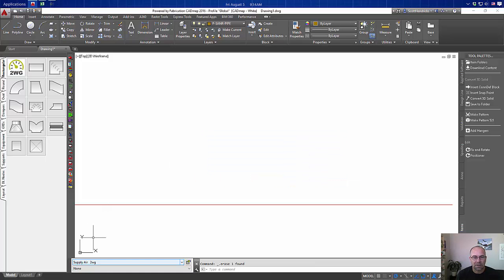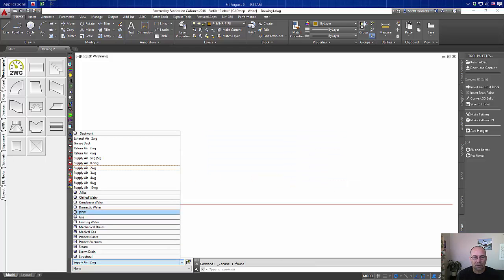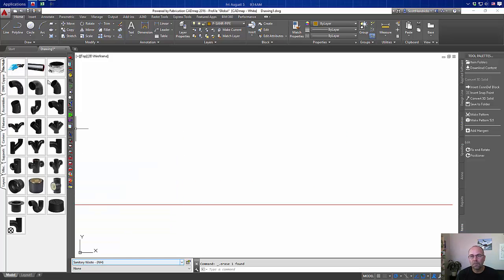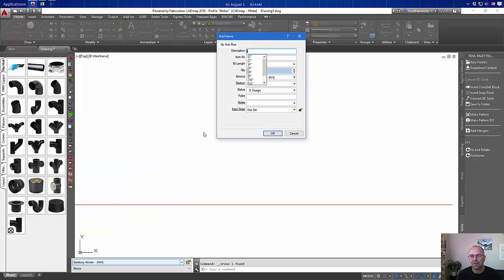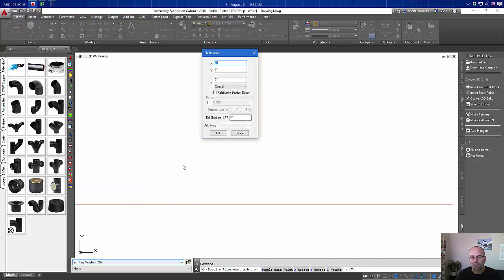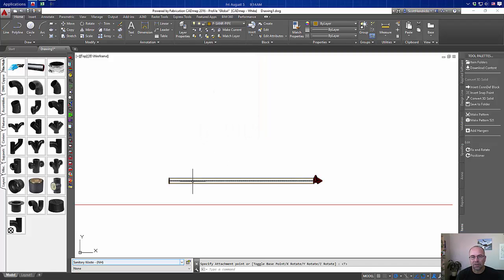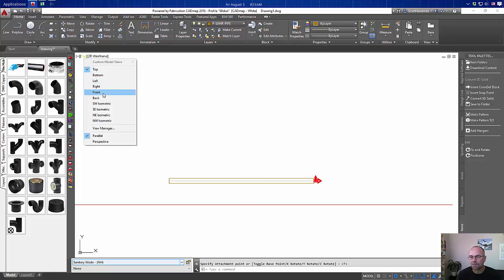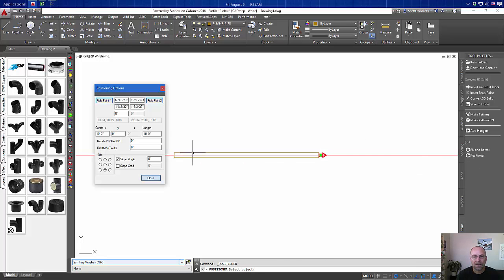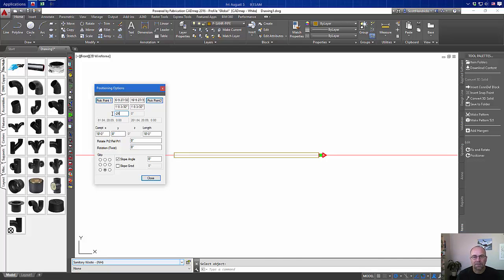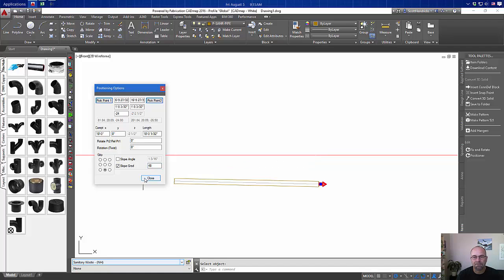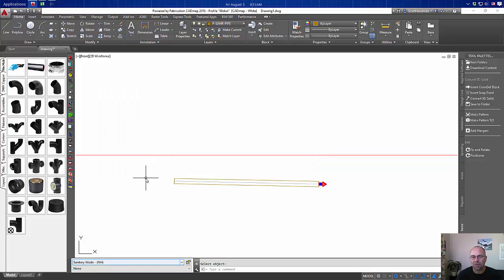Now let's take a look at an example for our plumbers out there. I'm going to place a piece of pipe. Again, we could have set some elevation and some grade, but we'll make some changes to this with the positioner. I'm going to go to a front view, start up my positioner, and set our elevation to negative 24. Give this thing a grade of 1 in 48 for a quarter inch per foot, and close.